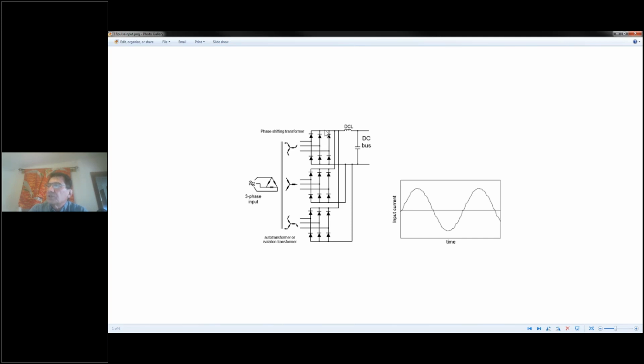Note that each of these diode bridges connects across the full DC bus. There's phase shifted secondary winding 1, there's phase shifted secondary winding 2. This is a diagram for 18 pulse, but we were talking about 12 pulse, so let's just ignore this for the moment. Notice that each of the diode bridges connects to the plus rail and to the minus rail, so they are in parallel. If we go back to the other diagram, you will see that those 2 diode bridges were in series. That's the main point that I'm trying to make here, because some manufacturers will use series diodes on the output of the phase shifted transformer. Some manufacturers will use paralleled diode bridges on the output of the phase shifted transformer.